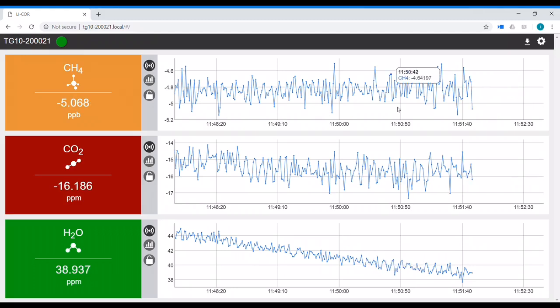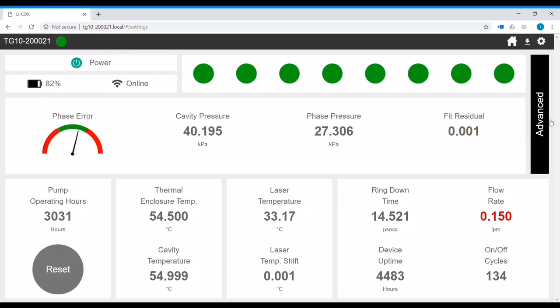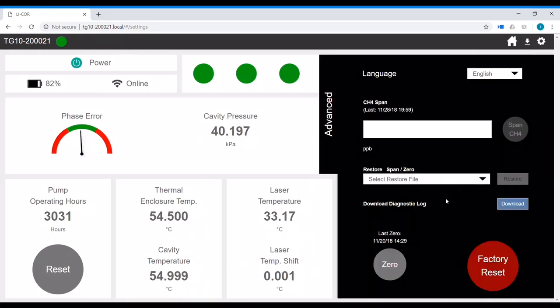So when you're ready to calibrate, once the gas readings are stable, you go to the settings page and go to the advanced page. One more additional detail: if you see a huge calibration offset or a huge offset in the measured values, maybe the instrument is using incorrect calibration, or it's doing something it's not supposed to do. So you can use this factory reset option, or you can revert back to previous calibration. You can choose from a list of calibrations and go back. So we're ready to calibrate this instrument, and we'll do the 0. That's the baseline calibration that we're doing.